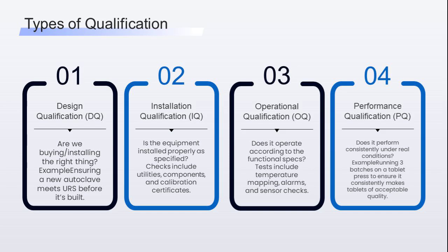OQ, operational qualification: does it operate according to the functional specs? Tests include temperature mapping, alarms, sensor speed, pressure, and RPM settings. PQ, performance qualification: does it perform consistently under real conditions? For example, running three batches on a tablet press to prove it consistently makes tablets of acceptable quality.